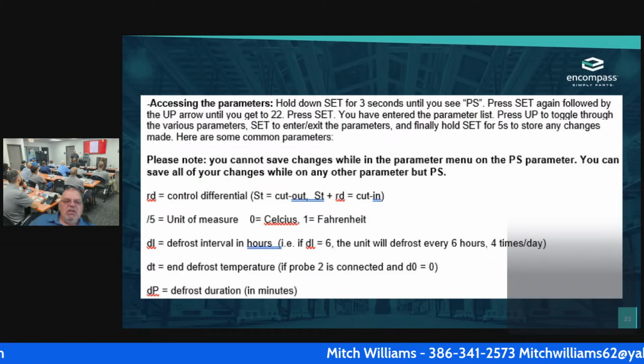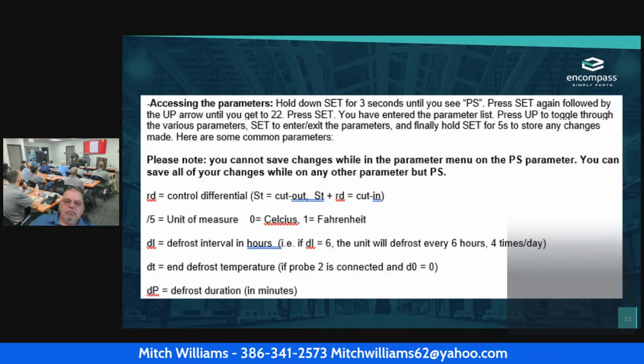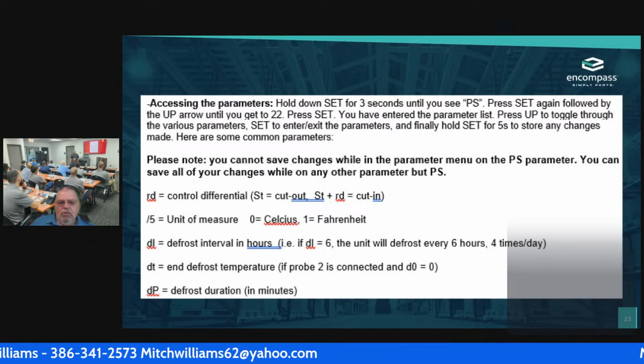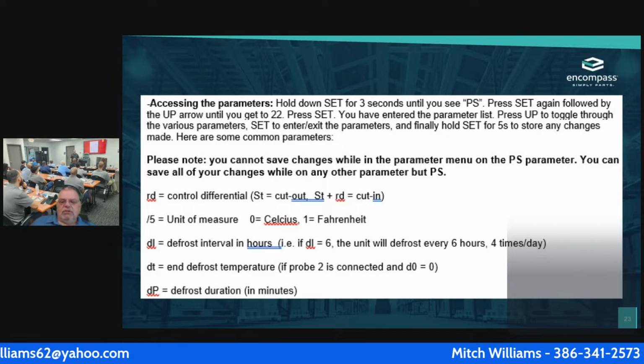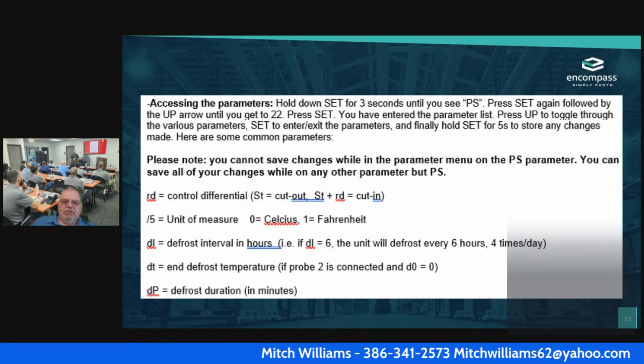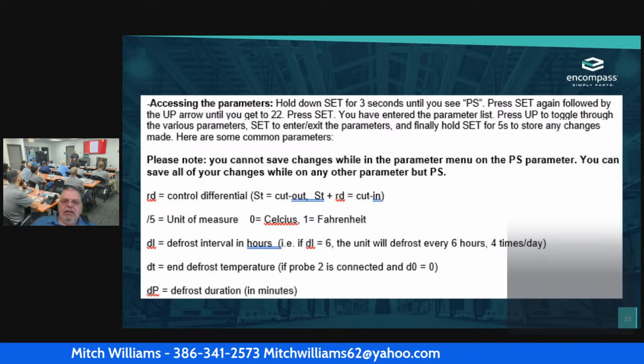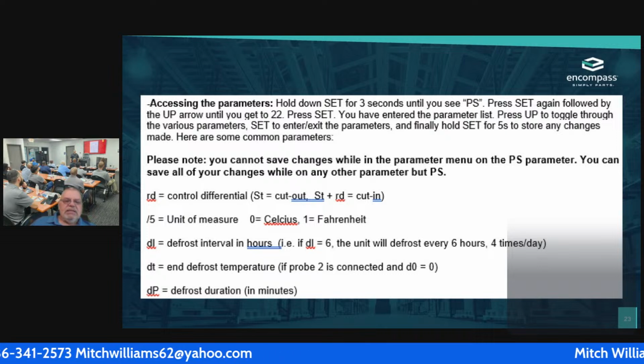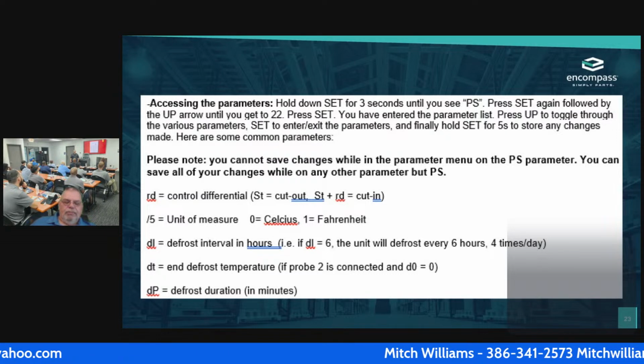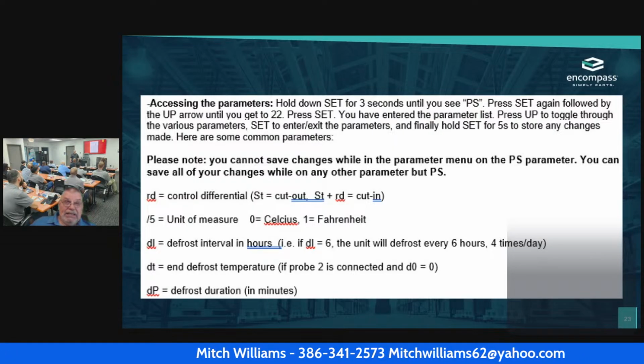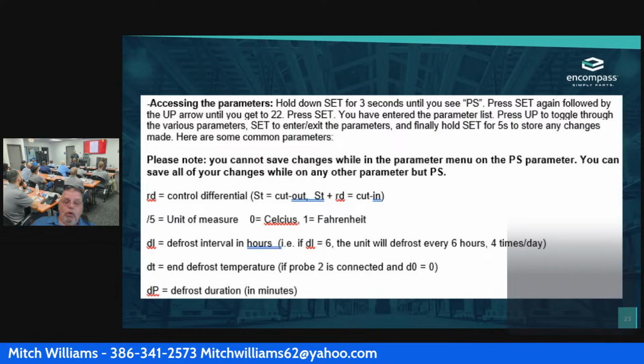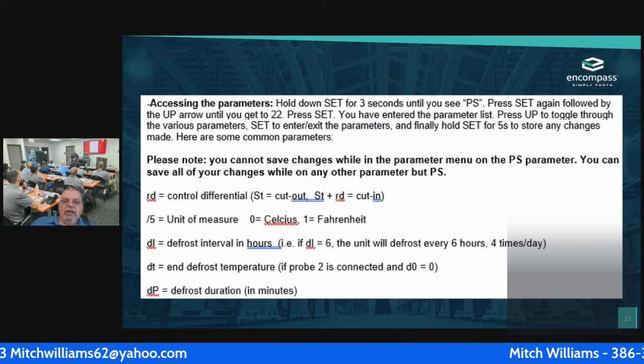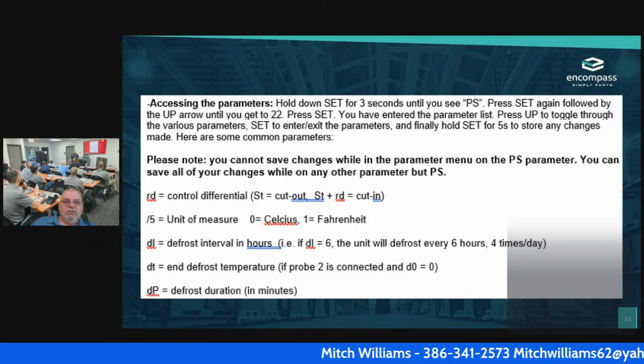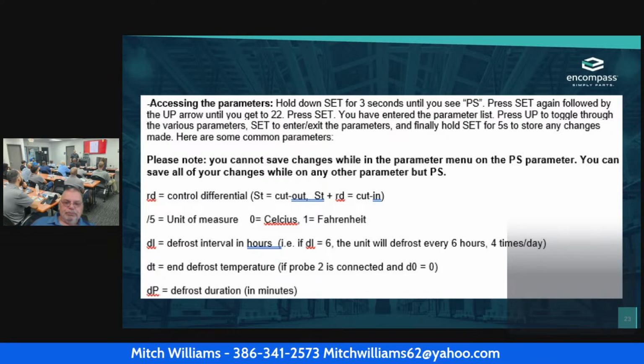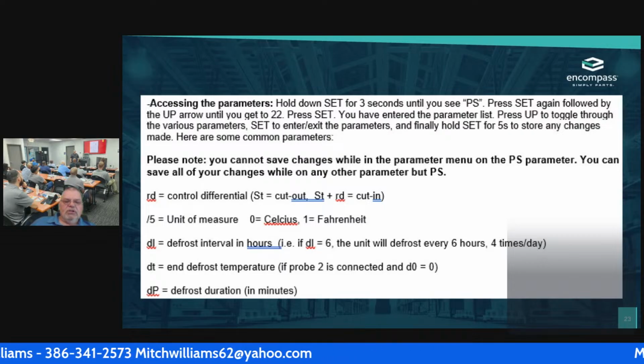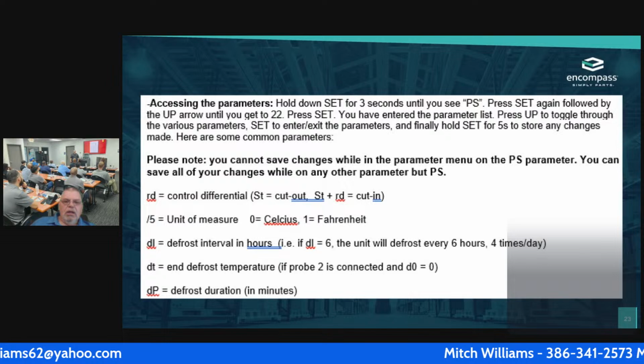Okay. If I have a DL, that's my defrost interval in hours. Okay. So if DL is 6, the unit will defrost every 6 hours, and that would make it 4 times a day. We all know that there's 24 hours in a day. Okay. If we have a DT, that is my end defrost temperature. So if my temperature rises, and like we said, it was above 40, it's set for 0. It's above 40. That determines my defrost cycle. Okay. My DP is my defrost duration. Okay. And that's in minutes.